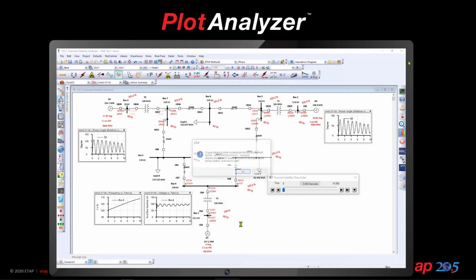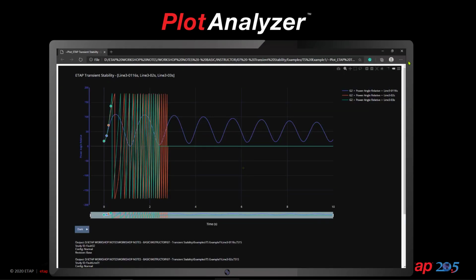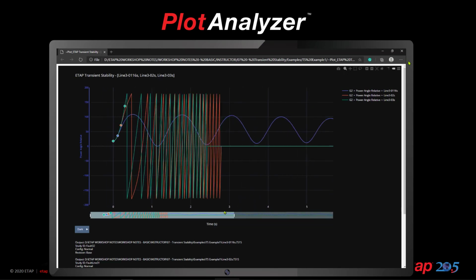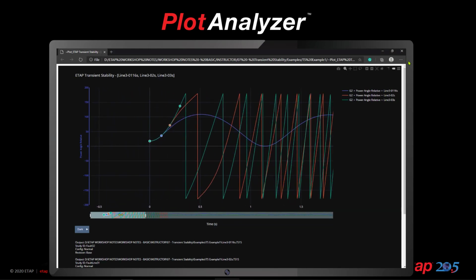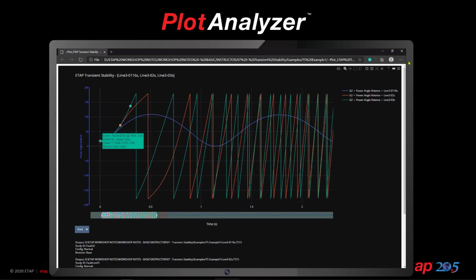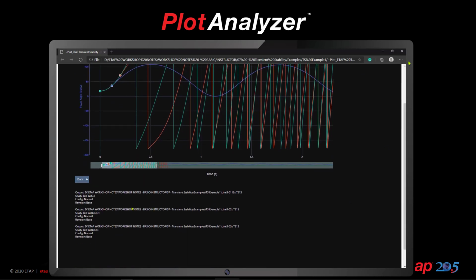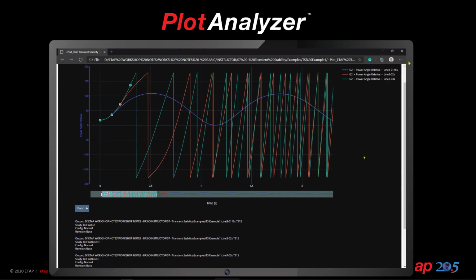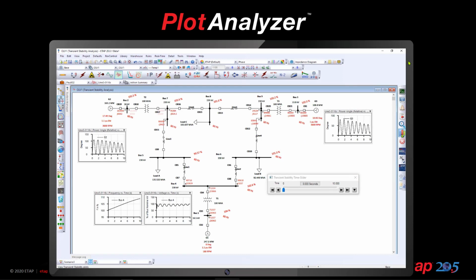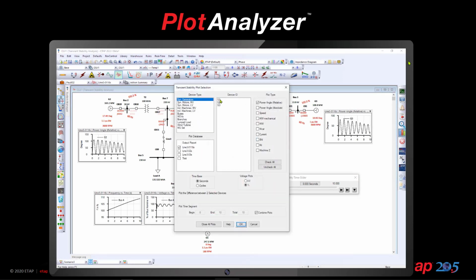If we go ahead and plot one of the generators with respect to different critical fault clearing times, we can see the relative power angle for time equals 0.3 seconds, 0.2 seconds, and then finally the blue line, which is at 0.116 seconds. We can also see the events directly on the chart, and these events are essentially coming from the study case in this particular system, or it may be coming directly from a relay. We also include the scenario information directly on the chart, so it makes it easier for you to print.